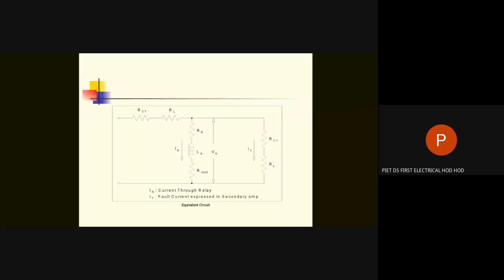Fault current for a large generator is usually 5 times the rated current, because the subtransient reactance Xd double dash is of the order of 20%. So IF would be 5 times the rated current. The fault current is 45,000 ampere for a 210 megawatt generator, and as it comes to the secondary, small IF, as it is shown, is 45,000 divided by 2000, that is 22.5 ampere.